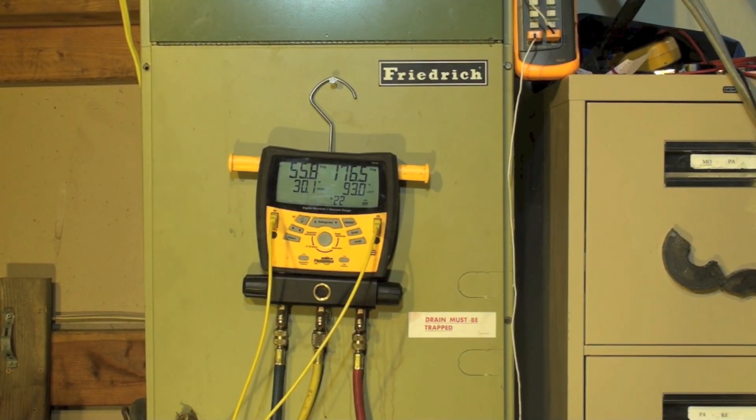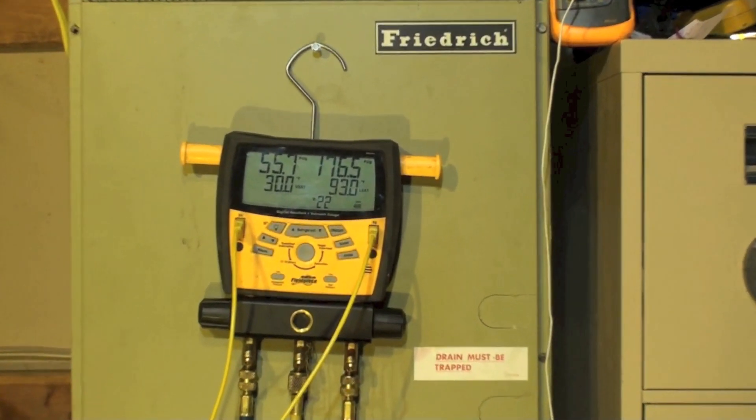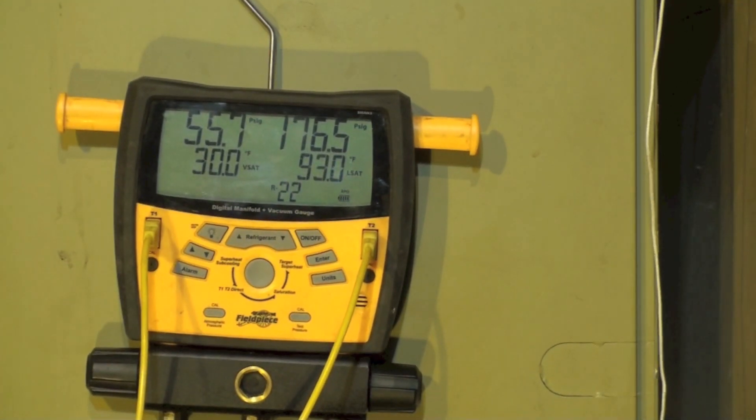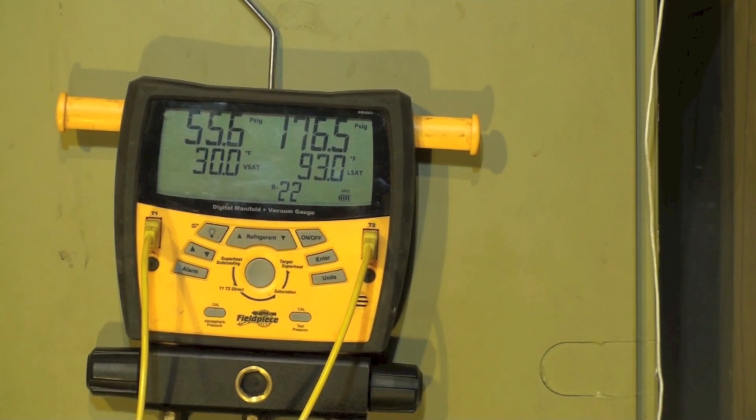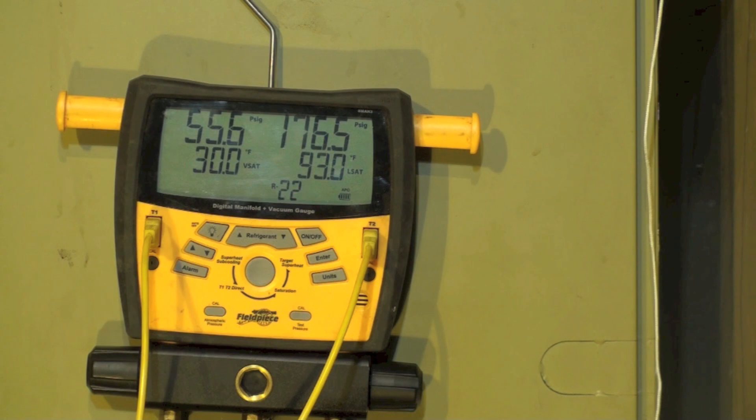I've set this up so you can see the saturated. On this I am evaporating at 30 degrees and I'm condensing at about 93. Our outdoor ambient is about 75, 76 degrees.